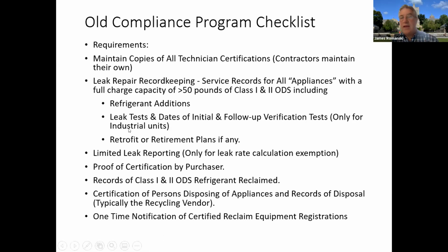The important parts were the initial leak test: they take out the refrigerant, fix the leak, put nitrogen in the system, and pressurize it. If it holds pressure, they fill it with refrigerant, and they come back within 30 days to do a follow-up verification to make sure it's not leaking again.